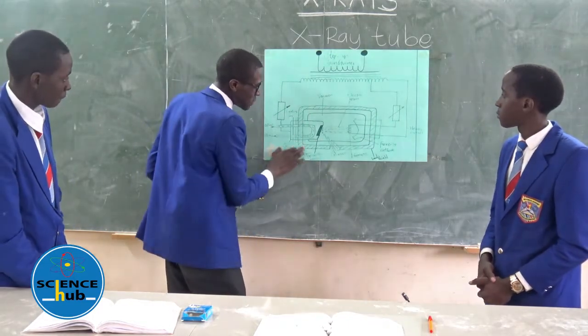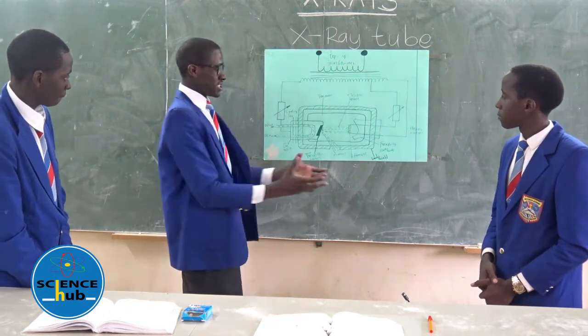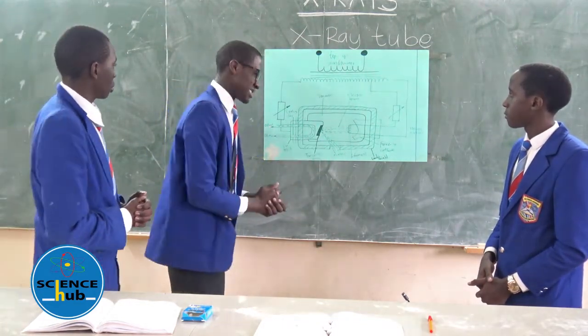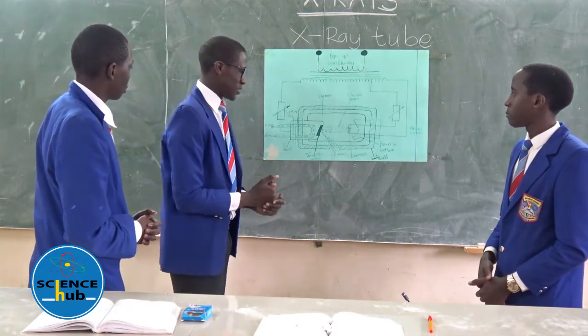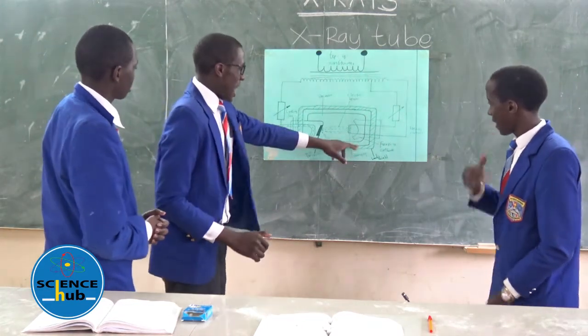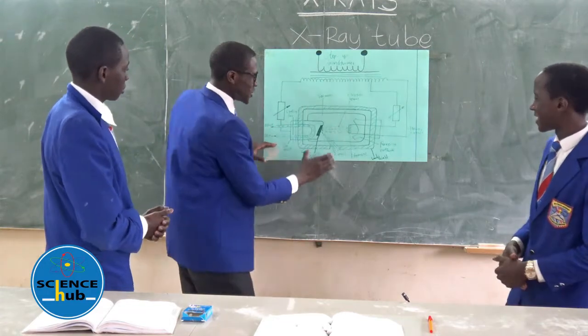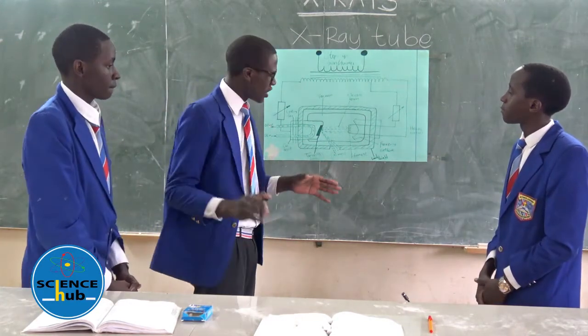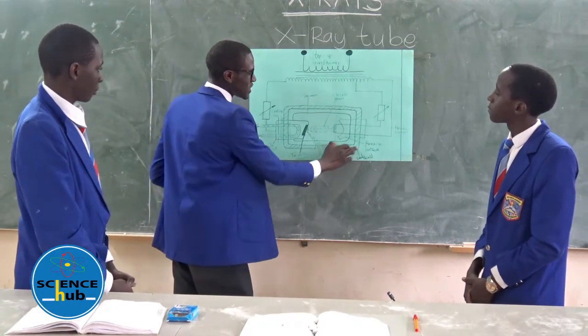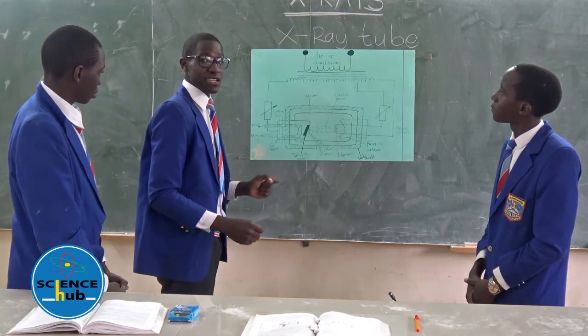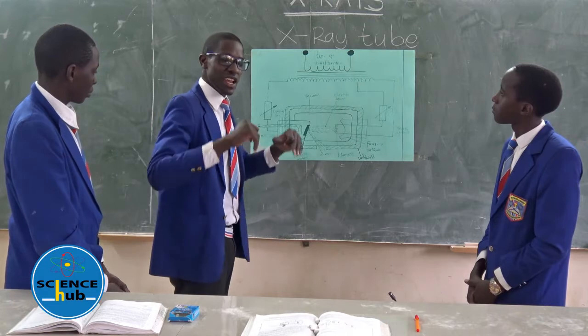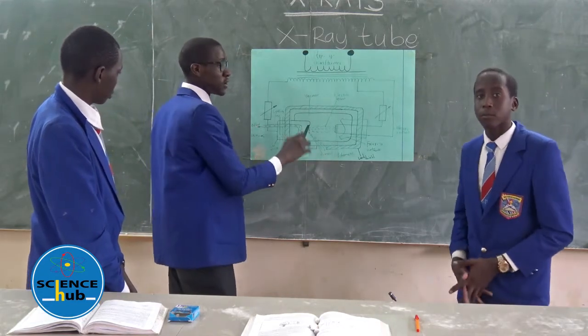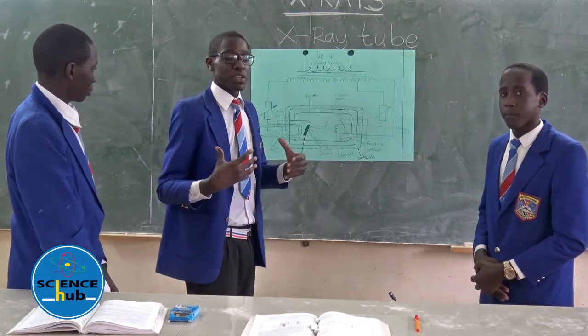The function of the lead shield is to absorb excess X-rays. Why do we use lead and not any other metal? We use lead because lead has a very high density. Therefore, X-rays can only penetrate in a minimal amount through the lead shield since it has a very high density — they penetrate at a very low rate, so a lot of the X-rays end up being absorbed rather than going to the surrounding.